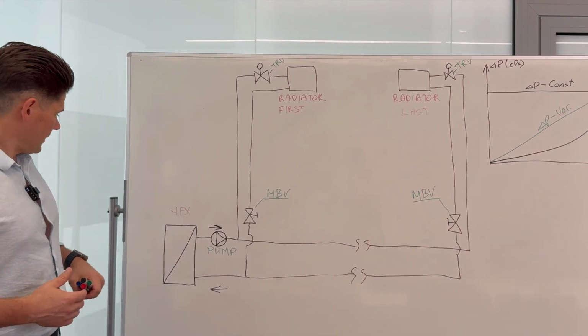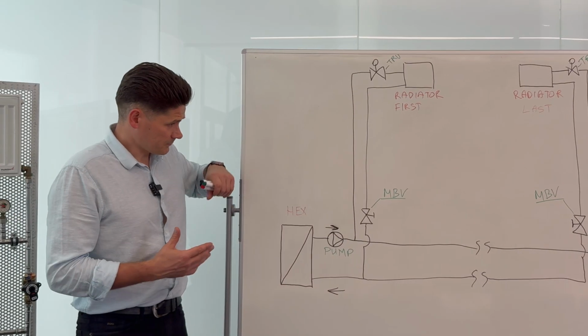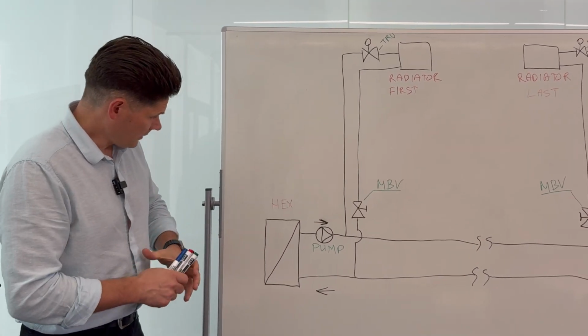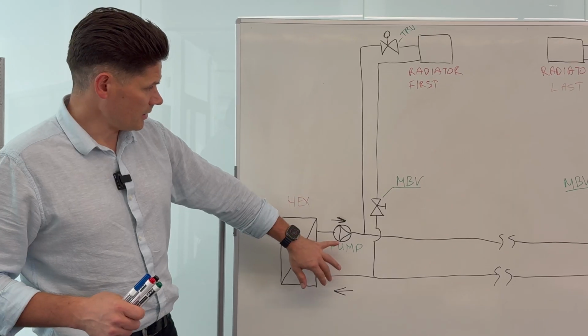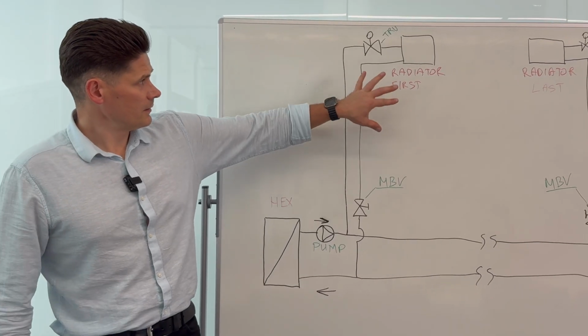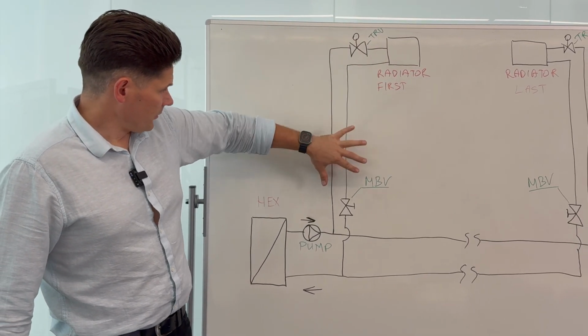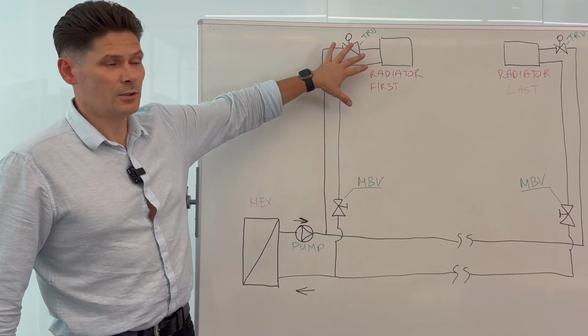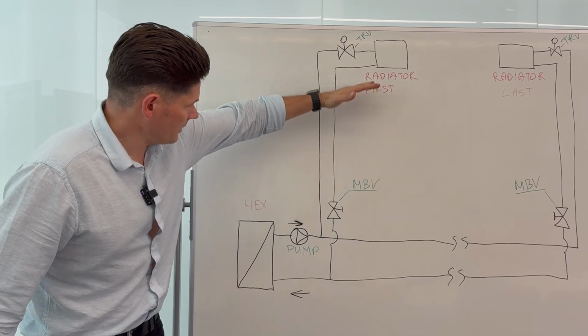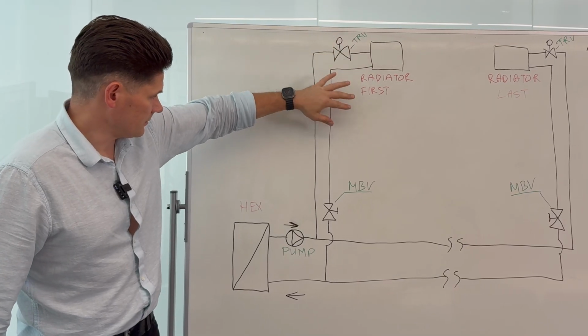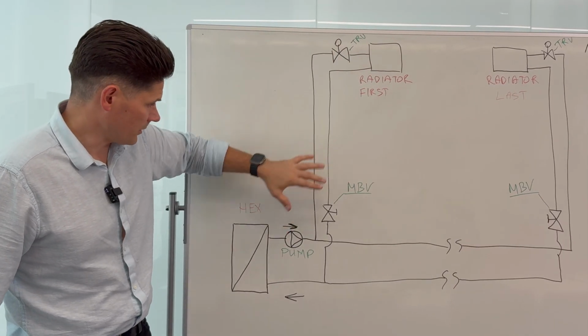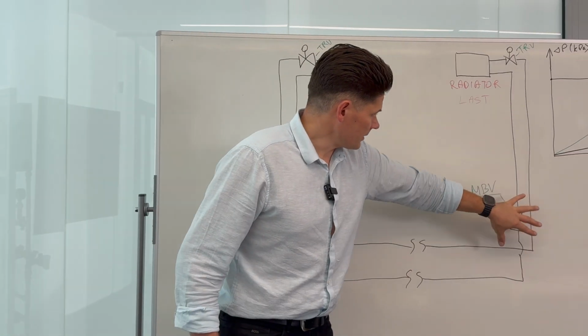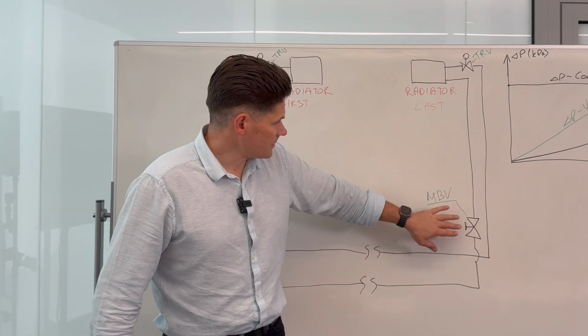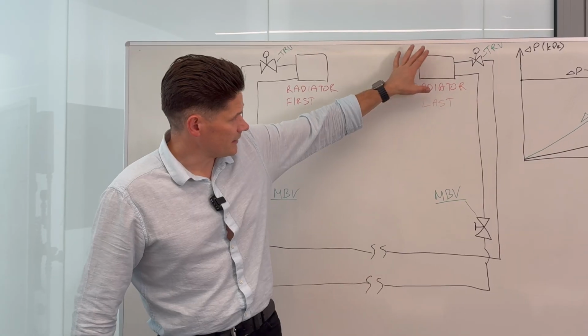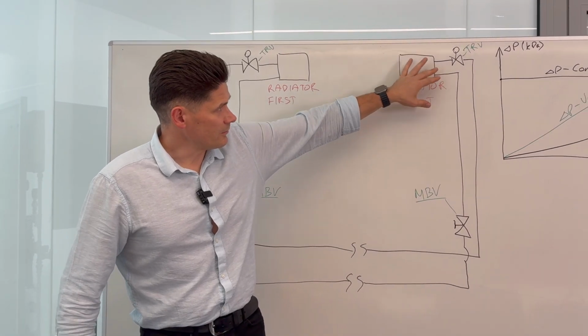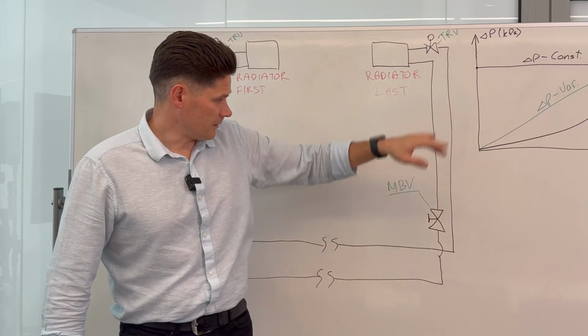So what I have here, I already prepared an example of a system. Here we have heat exchanger, circulation pump, manual balancing valve, first riser and radiator on top. Here of course we have some more radiators, but this one is the last on this riser, so this one is the most important. And here we have the last riser in my system, the last balancing valve, and the last radiator with thermostatic radiator valve.